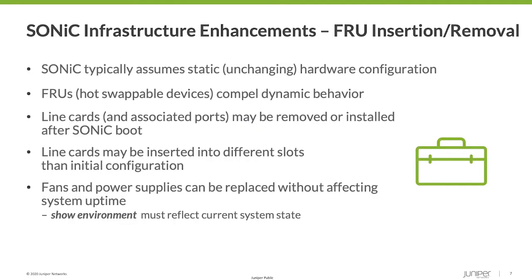Field replaceable units are a key characteristic of a modular chassis. This complicates SONiC a little bit. Since SONiC typically assumes static configurations, we had to extend SONiC to handle a more dynamic behavior. With FRUs or hot swappable devices, line cards and their ports may be removed or installed after SONiC boot. They may be inserted into a different slot. Fans and power supplies may be removed without affecting system uptime. The result is a very dynamic changing system.